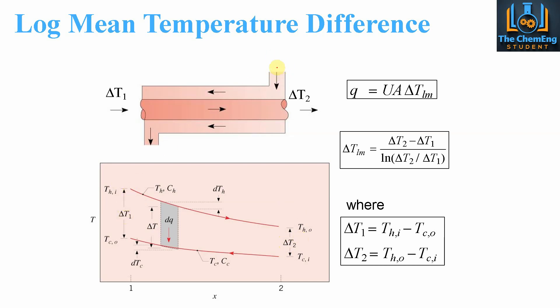In counter current flow, the cold stream comes in at one end, begins to heat up, taking heat from the hottest part of the system. It heats up gradually while maintaining a good delta T value throughout the heat exchanger, giving a more efficient heat transfer system. That's why most equipment in industry uses counter current flow — because we get a better delta T log mean value, as we don't have such a polarized temperature-distance profile.